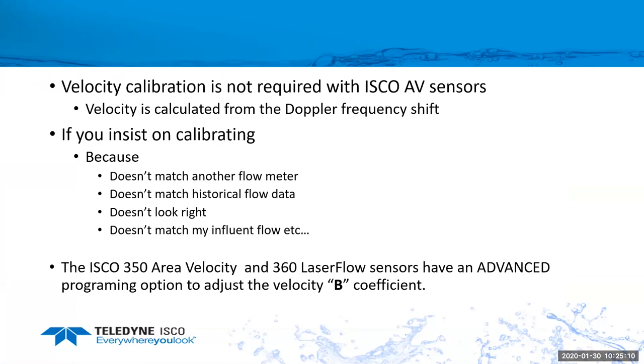But the question was, how do we calibrate velocity on an AV sensor? The velocity calibration is not required because it is the theory behind the frequency shift. We can calculate the accurate velocity based off the frequency shift. So it doesn't really matter if I'm outputting a 1 megahertz signal or a 500 kilohertz signal. It's reading the Doppler effect, or the frequency shift, to come up with the velocity.